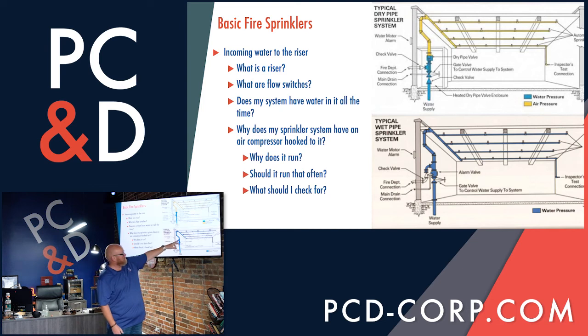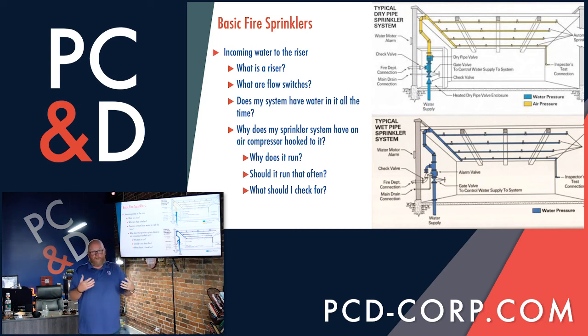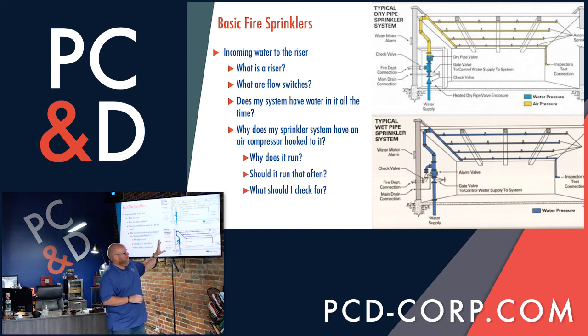So you have your risers that come in, you basically have your distribution that goes out throughout the building, and you have your sprinkler heads. These heads are sitting there ready to work the way your wet systems are set up. Something else that Travis touched on earlier in our training: this isn't like in the movies, where when you have a fire, all of a sudden every head in the place goes off. That's not how sprinkler systems work. Just so you know, with wet systems, water is in here everywhere all the time, ready to discharge.